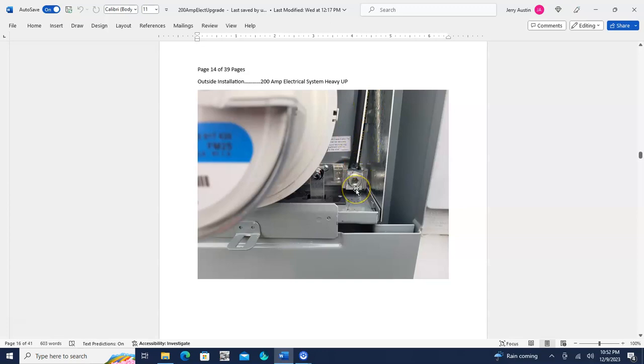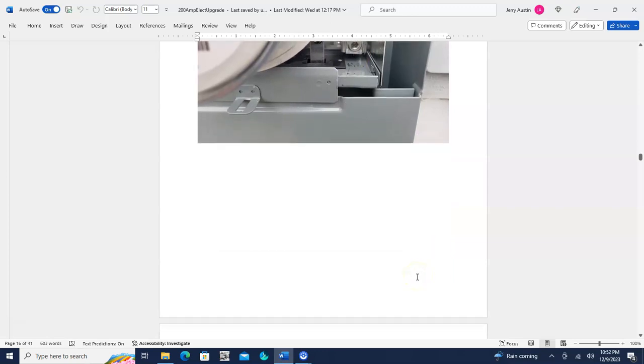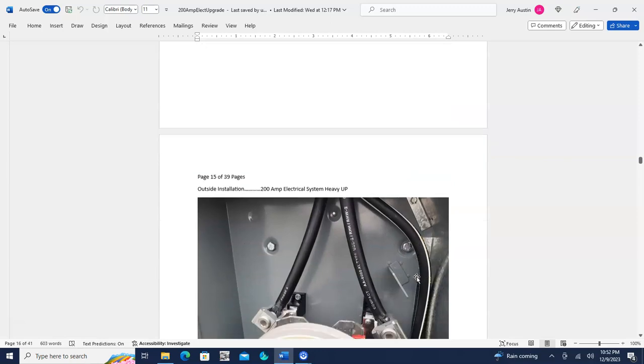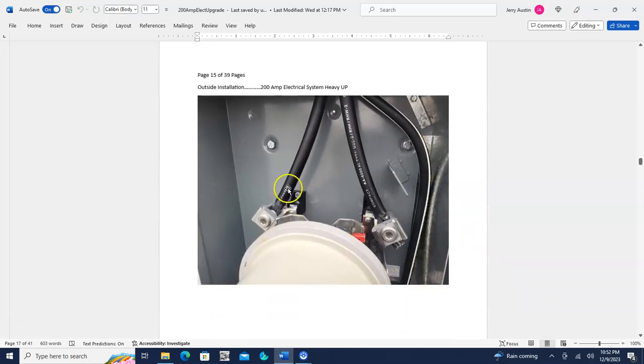You can see where it's hooked in here on the meter base. These are the two power leads coming in from the electric line coming down through that 2-inch metal pipe, and you can see where they're hooked in here on top of the meter base. And this is the ground wire that goes down and hooks into the bottom of that.